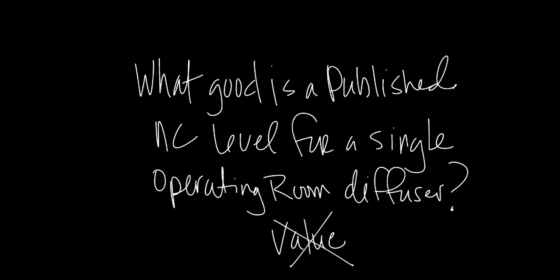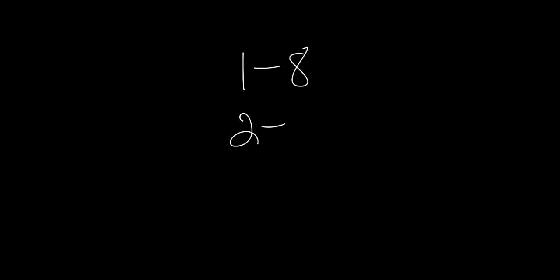So what should we do? Ideally, we should ignore published NC levels for diffusers in this type of application, and instead look at sound power levels. Although manufacturers typically don't publish sound power levels for diffusers, some manufacturers have selection software that can provide these values. If they don't, it can often be requested from them. They should be able to provide octave band sound power levels for either bands 1 through 8, bands 2 through 7, or possibly only bands 4 through 6. Diffusers typically set their sound levels in bands 4 through 6, so that's okay.